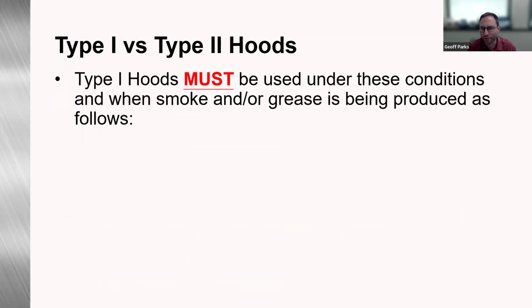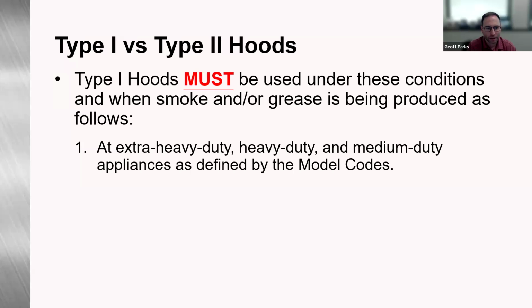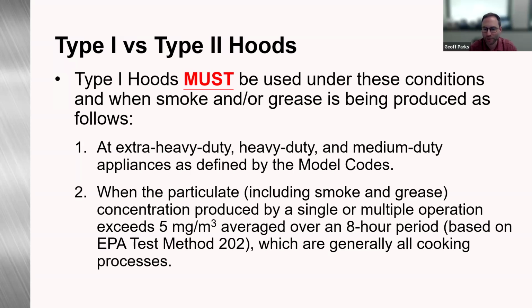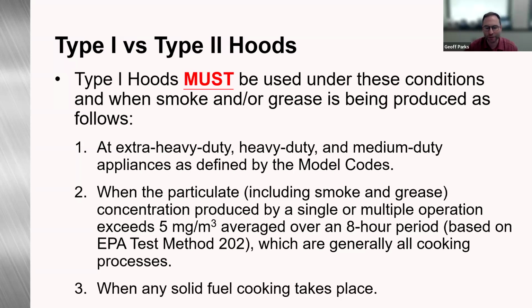So type 1 hoods must be used under these conditions, when smoke and/or grease is being produced: at all extra heavy duty or medium duty appliances as defined by the model codes, and when the particulate, including smoke and grease concentration, produced by a single or multiple operation exceeds 5 milligrams per cubic meter, averaged over an 8-hour period based on EPA test method 202. Generally, all cooking processes would generate this 5 milligrams per cubic meter. And when any solid fuel cooking takes place, a type 1 hood must be used.